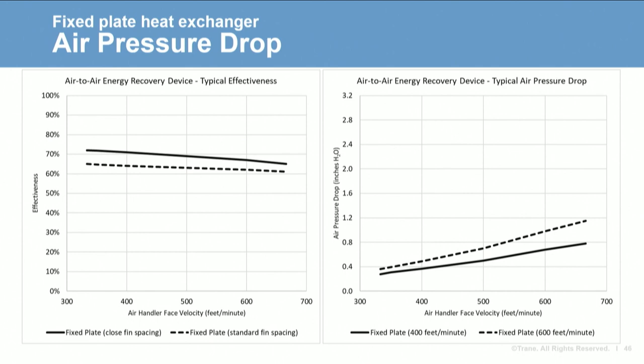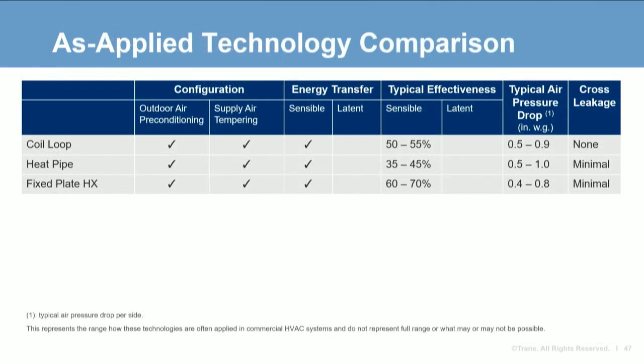Face velocity does have a large impact on pressure drop: reducing the air handler face velocity from 600 to 400 feet per minute will cut the air pressure drop in half. Fixed plate heat exchangers can be provided in outdoor air preconditioning and series configurations. They only transfer sensible energy. Sensible effectiveness ranges between 60 and 70%, while air pressure drop typically ranges from 0.4 to 0.8 inches of water. Airstreams are separated, resulting in minimal cross leakage.